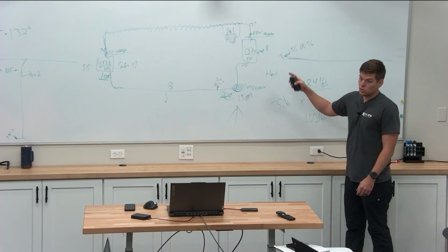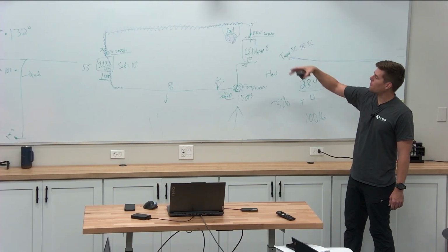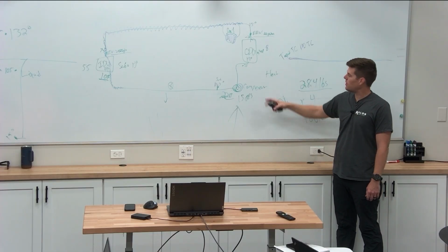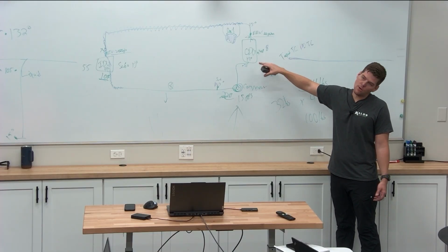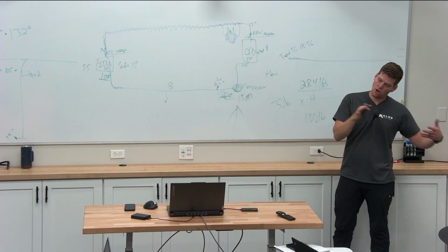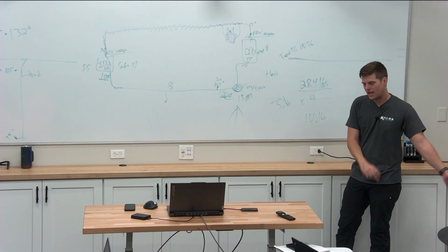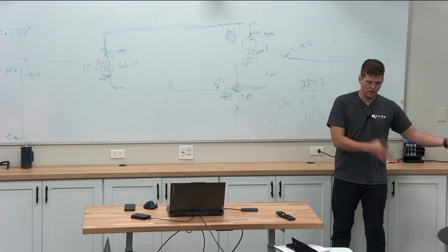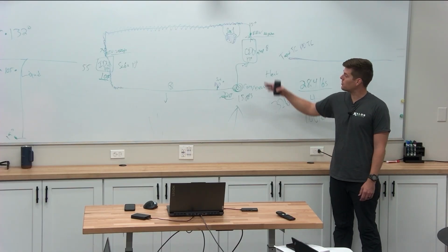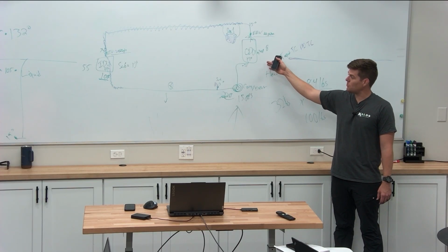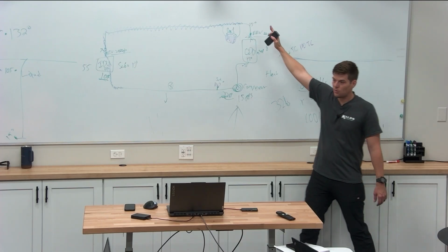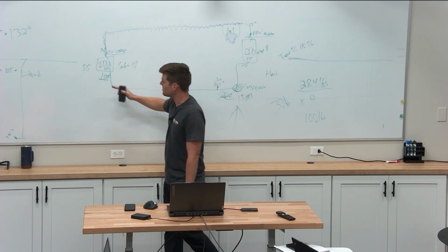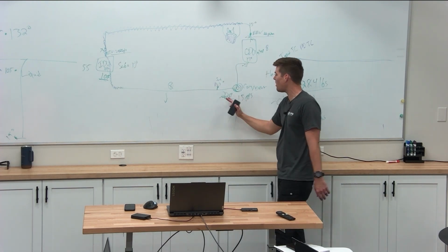So we look at this, and at first it's okay. Maybe the valve pulses were at 200, and then it floods, so it says, okay, I'm flooding, let me shut my pulses down lower. So it goes to 180, 140, 120, it's still flooding. It goes to 20 pulses, and then the superheat gets better. But what happens when the superheat gets better? Guess what? It starts to stack liquid on this side, and it stacks and stacks and makes it all the way back to the compressor.